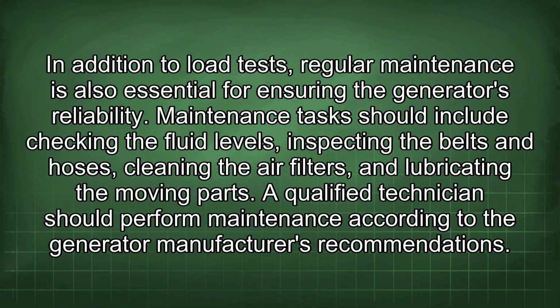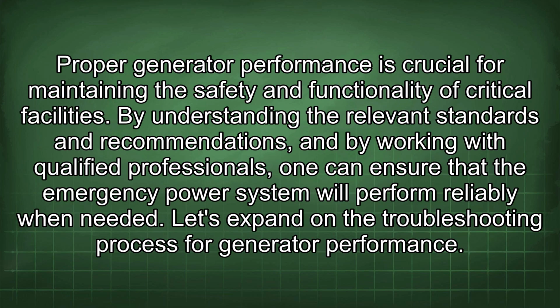In addition to load tests, regular maintenance is also essential for ensuring the generator's reliability. Maintenance tasks should include checking the fluid levels, inspecting the belts and hoses, cleaning the air filters, and lubricating the moving parts. A qualified technician should perform maintenance according to the generator manufacturer's recommendations. Proper generator performance is crucial for maintaining the safety and functionality of critical facilities. By understanding the relevant standards and recommendations, and by working with qualified professionals, one can ensure that the emergency power system will perform reliably when needed.